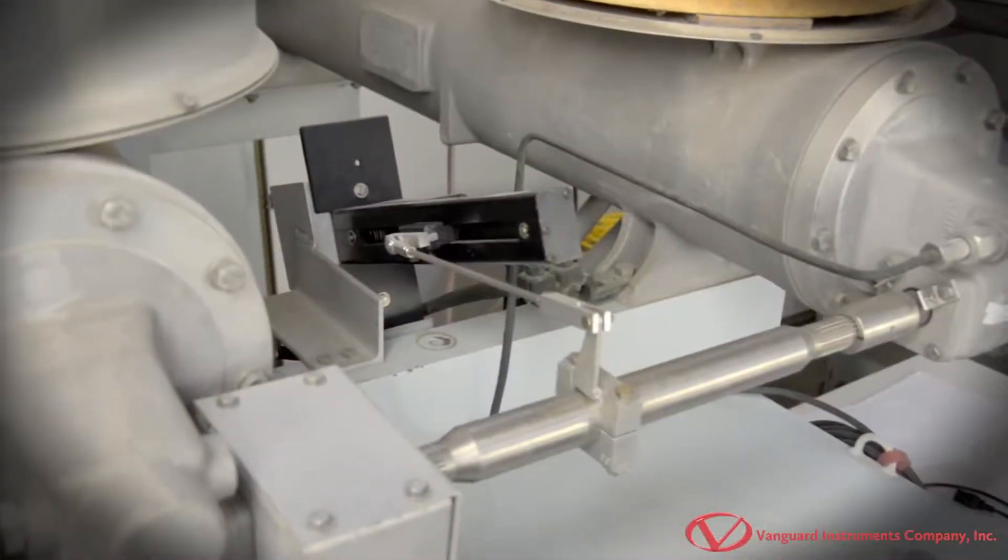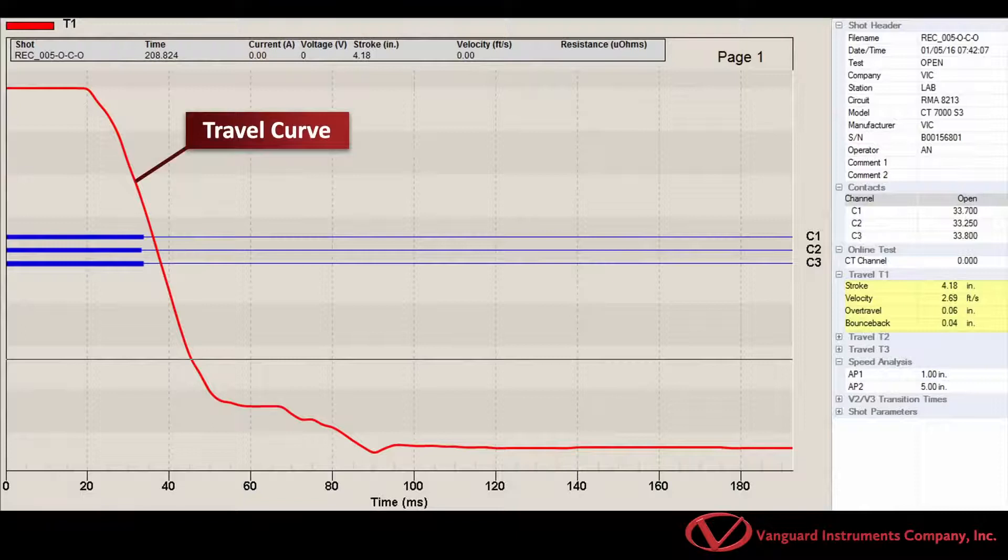Motion tests performed with a transducer are used to check the mechanism stroke, velocity, damping, and over-travel against the manufacturer's specifications.